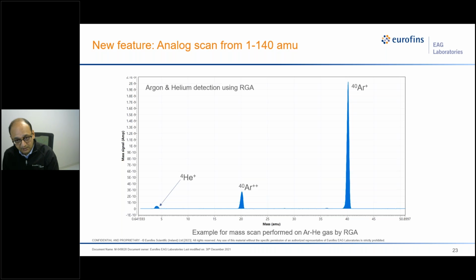And why are we doing it? Because we are only measuring the calibrated gases. But what if there is some unknown gas? What if something is not as expected? So we have another set of eyes on our gas. We do this 1 to 140 AMU scan at the end of each analysis, including calibration and samples. So if you want that information, we have it, and we can provide it as a supplementary report.